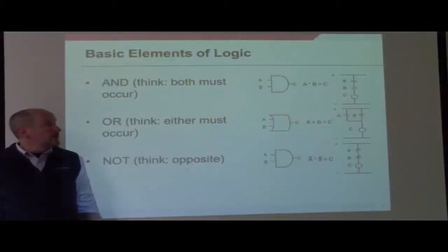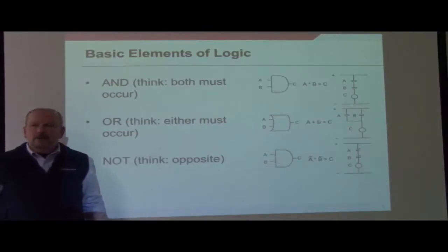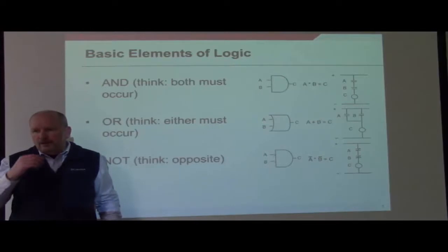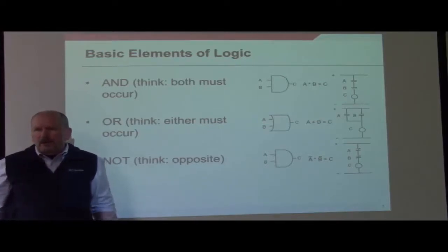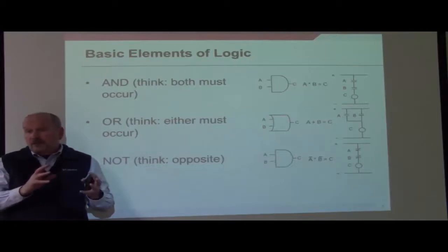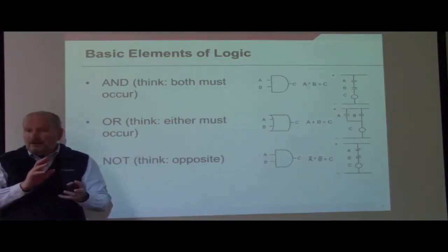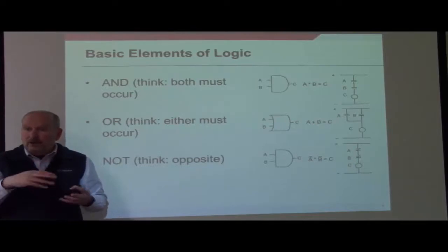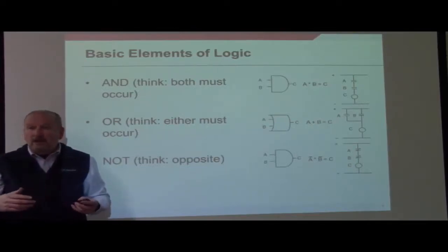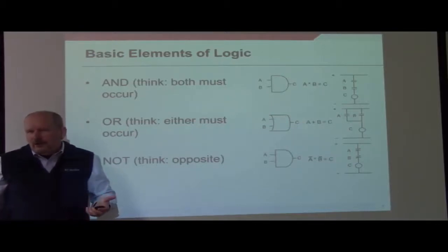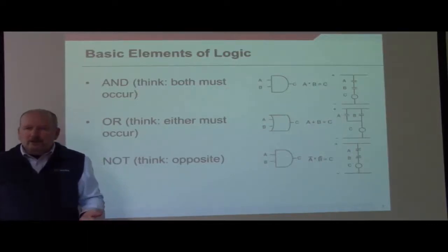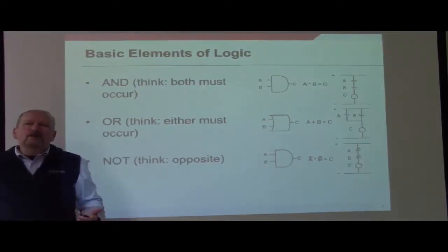Okay, next I'd like to introduce some of the basic elements of substation logic. And there are three basic formats that we use for substation logic. Probably the most common is ladder logic, and that's really where we show our DC schematics. And it's really nice because it shows physically all of the different devices that we then connect with wires to execute our scheme. Now, with the advent of programmable devices, because when I started doing this 25 years ago, we really didn't have anything programmable. But now it's completely changed, and with modern microprocessor relays, quite a few features of our relay schemes have to get programmed in.